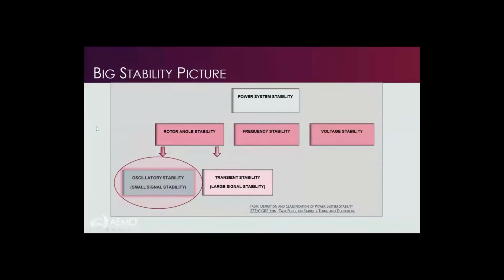Where in the big picture does oscillatory stability sit? So we have a definition of power system stability by IEEE and CIGRE. And there are three types: rotor angle stability, frequency, and voltage stability. Oscillatory stability sits under rotor angle stability, as well as transient stability. They are both short-term phenomena, whereas frequency stability and voltage stability can be long or short, depending on what's happening.